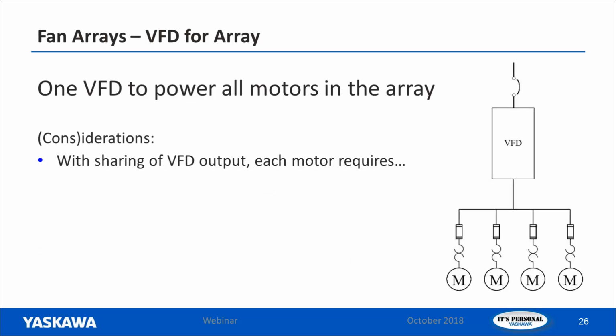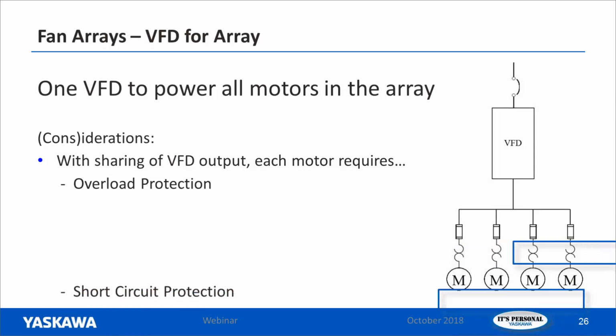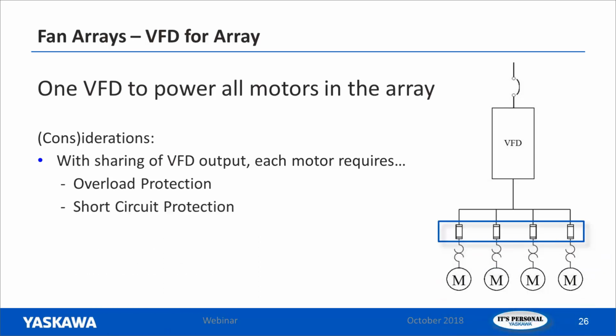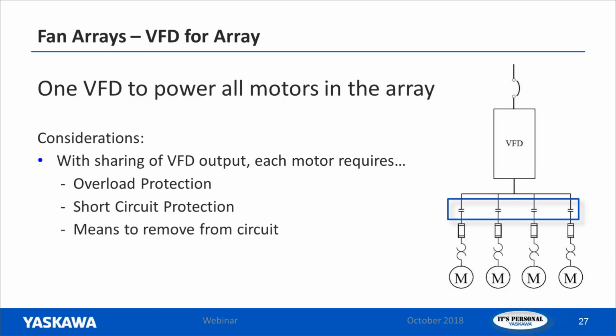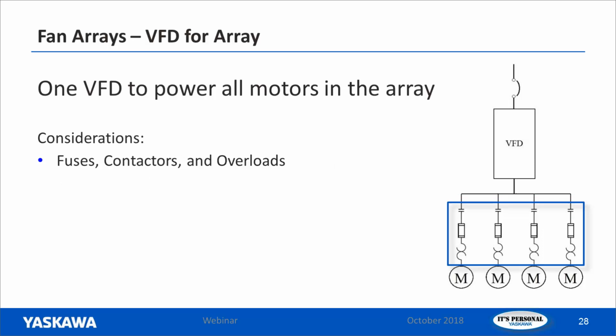One of the things you do have to consider when you're using a VFD to power all the motors in the array is that with the sharing of the VFD output, each motor is going to require its own overload protection, because the VFD only sees one load on its output. So now you do have to individually protect the motors. You've got to have an overload for each motor, and then fuses for short circuit protection, and a means to remove an overloaded motor from the circuit so that you can still run the remaining motors. So this would be fuses, contactors, and overloads.